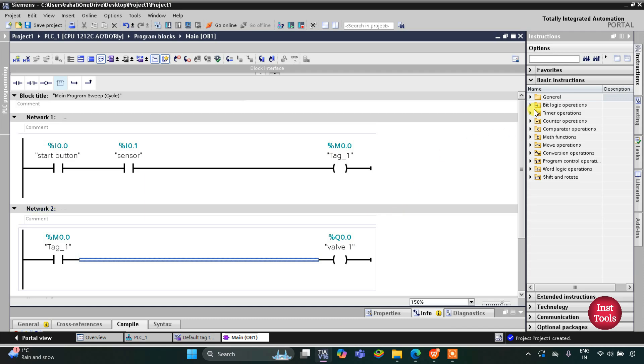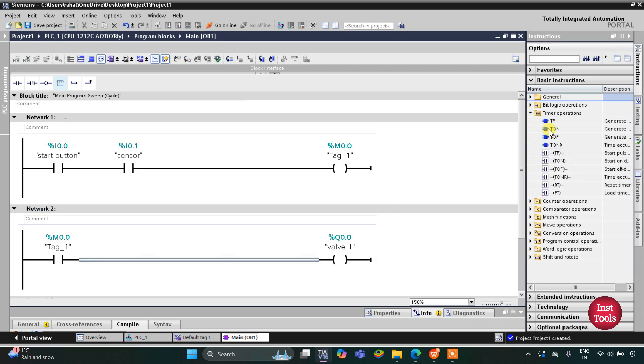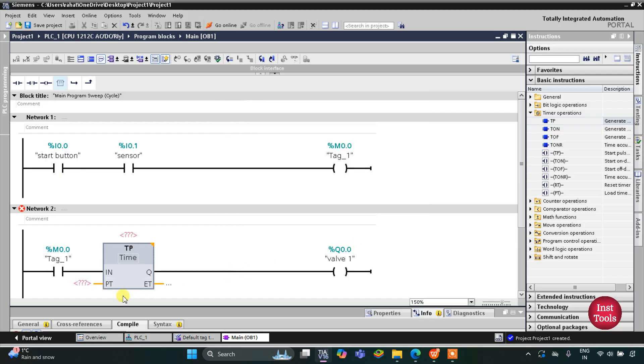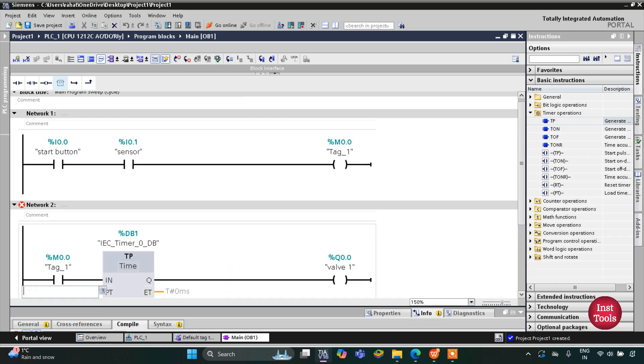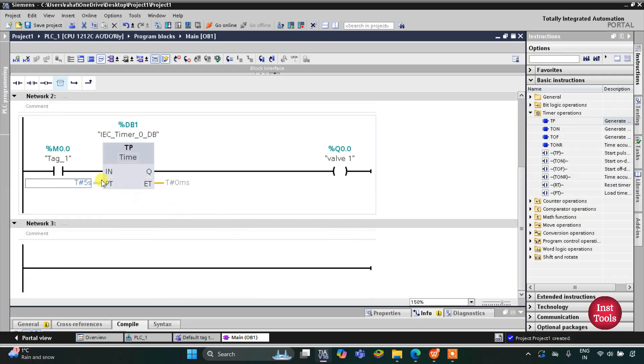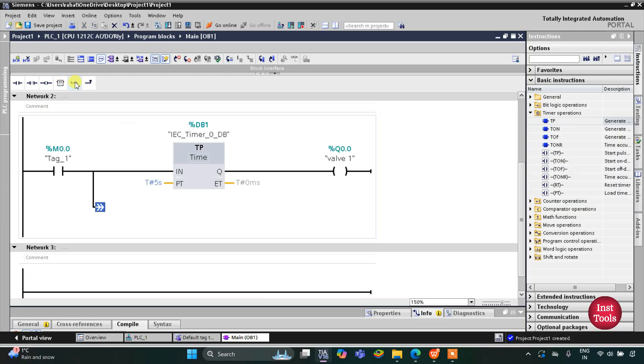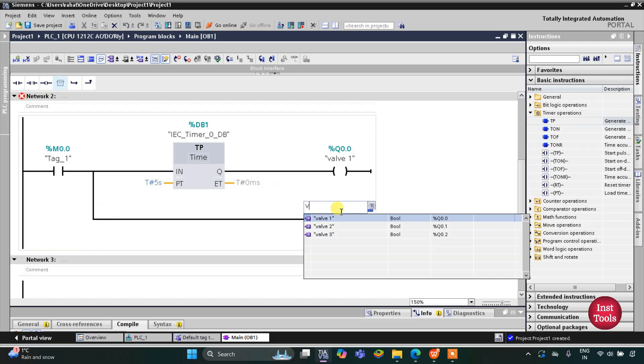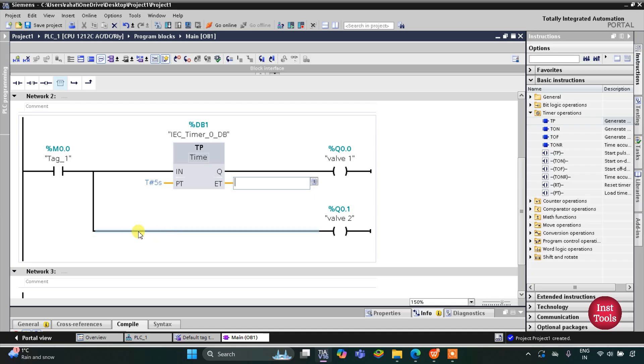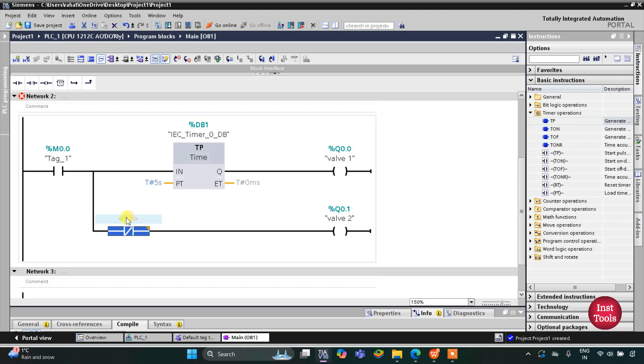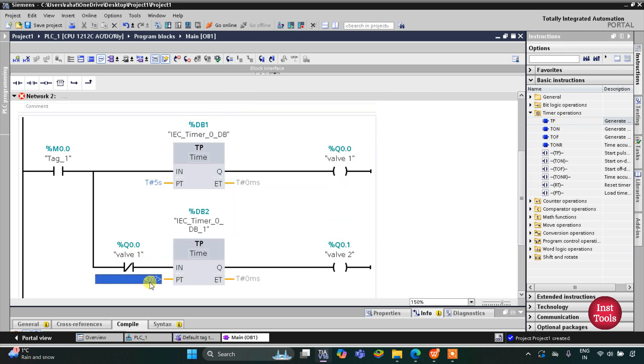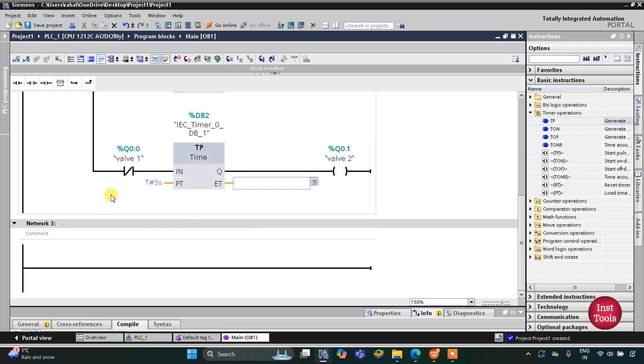Valve 1 will operate for five seconds, for which we will use a timer operation TP with a preset value of five seconds. Then I will open a branch and add a coil for Valve 2. Valve 2 will operate when Valve 1 is off, so I will insert a normally closed contact representing Valve 1. Valve 2 will turn on for five seconds using a TP timer with a preset value of five seconds.